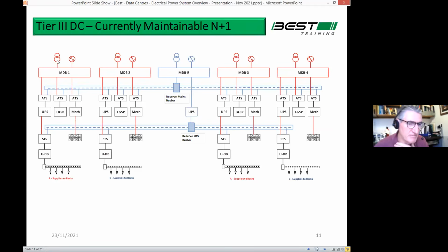So you have your transformer converting medium voltage to low voltage. You have your generators feeding into the board. Now, if we look at what happens, each board feeds down through this thing called an ATS. I'll explain about that in a minute. It stands for automatic transfer switch, but the power comes through that and then feeds the UPS system, which feeds the servers. L and SP stands for lighting and small power. So all the lighting in the building, small power, small fans and things like that. And then the Mech refers to the mechanical cooling system. So they're the 3 main loads you have fed off each board in each data hall: UPS, lighting and small power, and the cooling system, whatever that is, chilled water, fans, whatever it is.